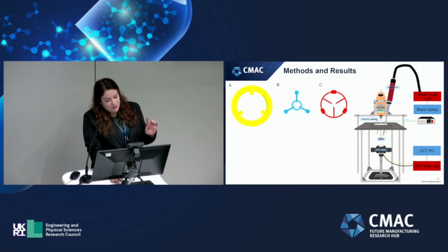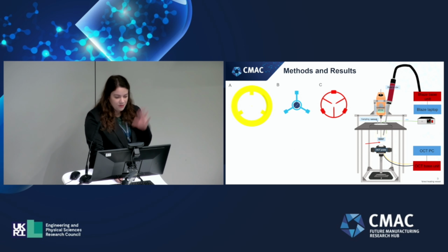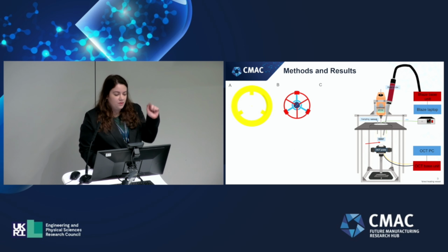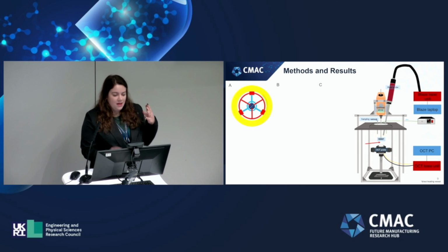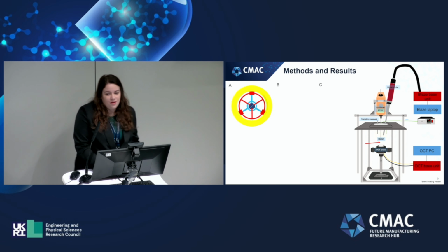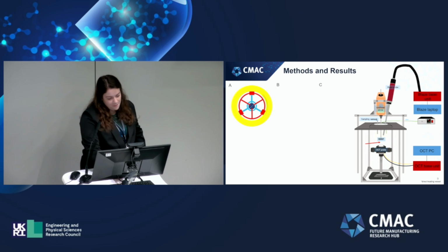You've got part A, which would sit in the bottom of the vessel. You would then put the tablet on part B, put the lid, part C, on, and all of this would go into part A, which would already be at the bottom of the vessel. You would then start all of the various probes, and that allows us to capture really high quality swelling data.